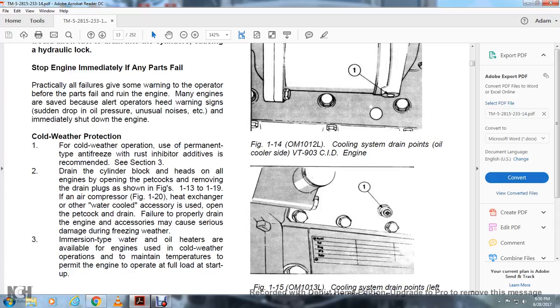Cold weather protection. Cold weather operation may use the permanent type of antifreeze with the rust inhibitor additive recommended in Section 3. Drain the cylinder block and heads on all the engines, operating the petcock by removing the drain plugs as shown in Figures 1-13 through 1-19. If any air compressor, heat exchanger or other water-cooled accessories are open, use the petcock drain. Failure to properly drain the engine and accessories may cause serious damage during freezing weather.